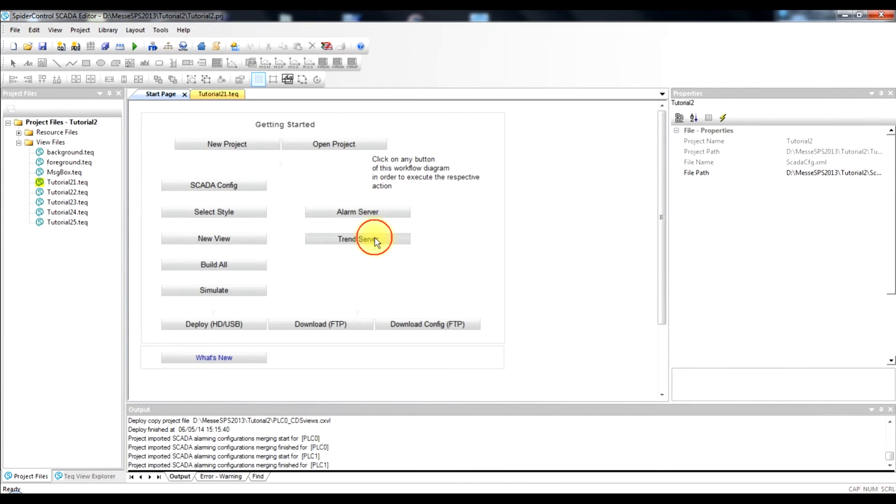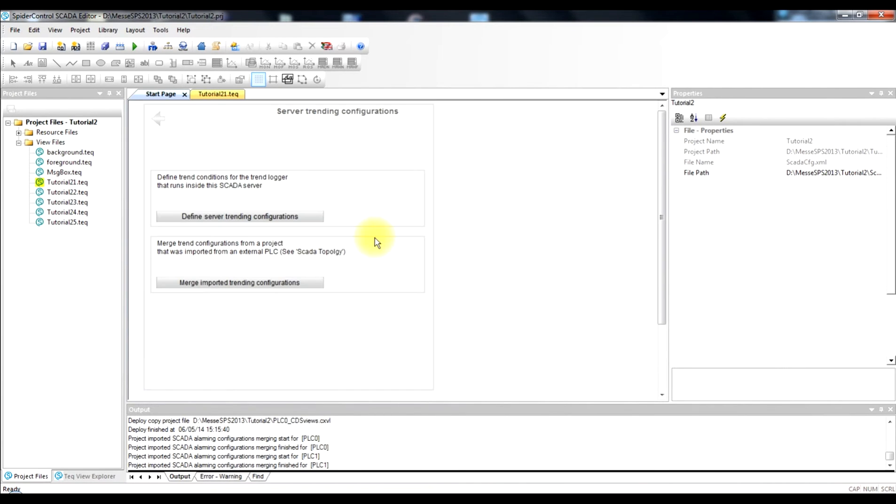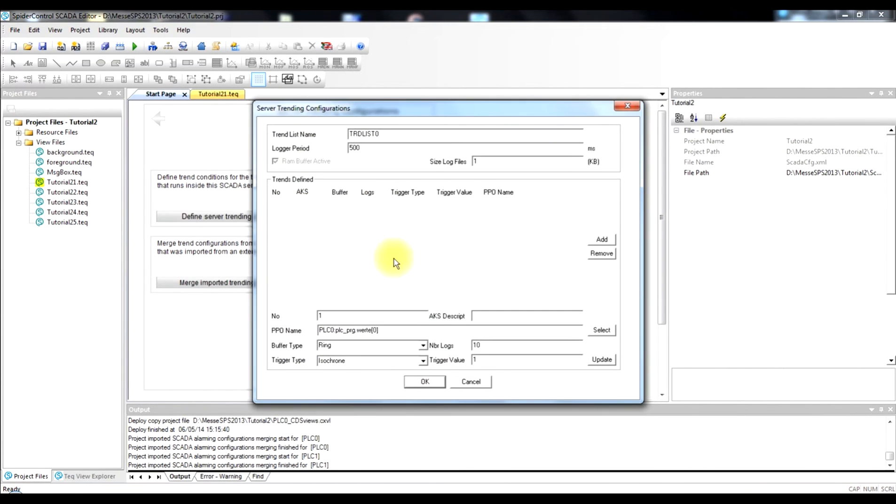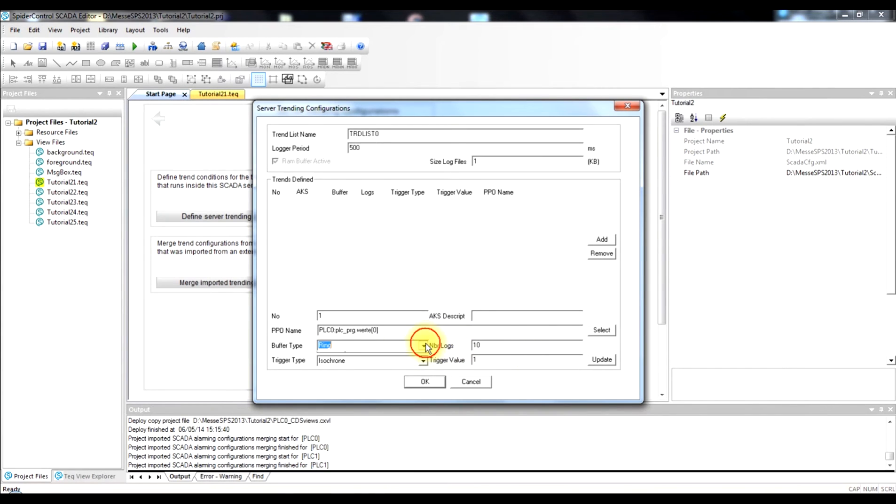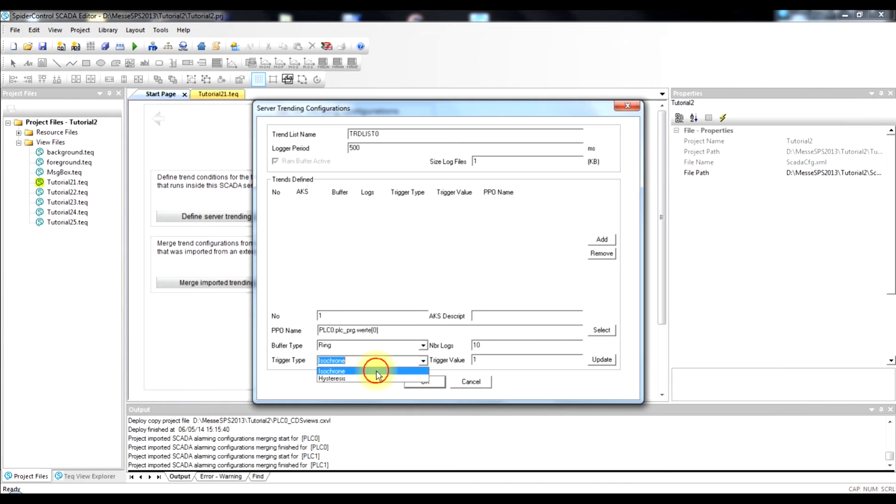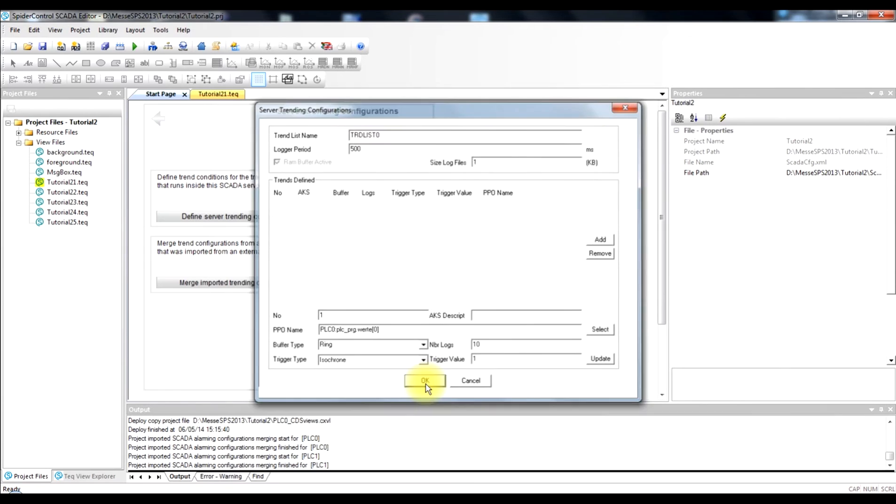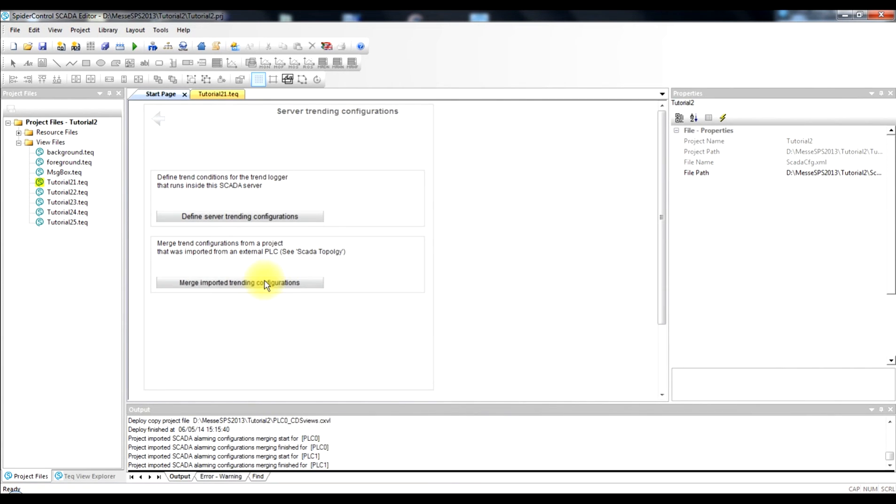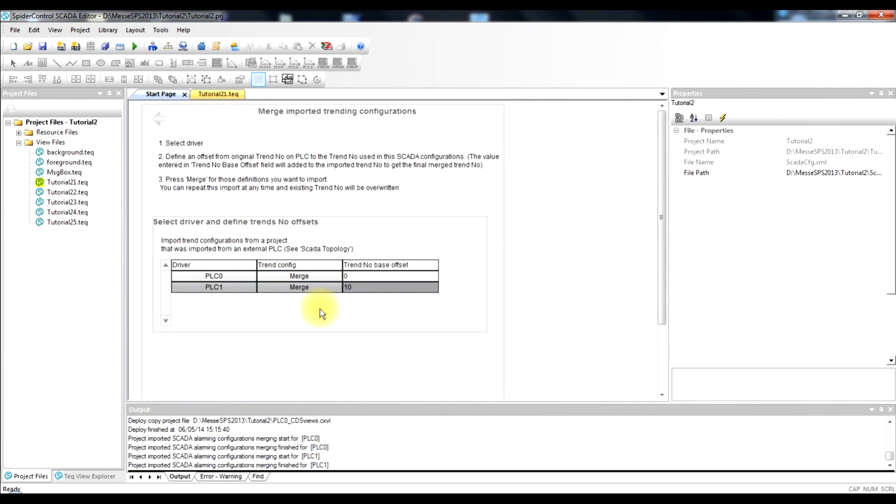The same procedure can be done in a similar way for trends. So the manual way to define a trend is done using this dialog. You can choose as well a process point that should be recorded as a trend. You can define the way how to record the trend. So we have an isochronous way of just having a fixed sample rate or there is a hysteresis based recording which triggers if the value changes by a certain amount. So this is the way how this trending recording would be done manually.